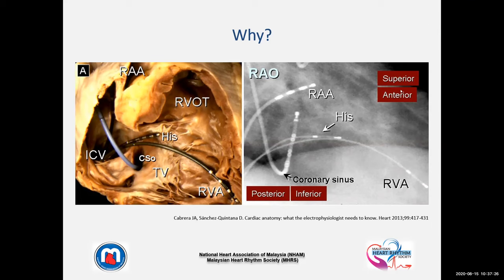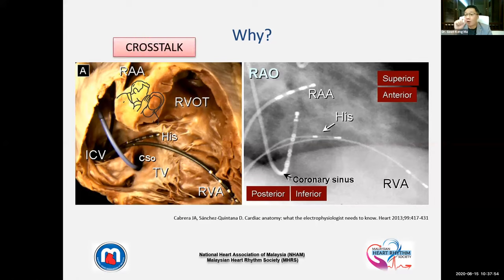Look at this. The right atrial appendage, which is the usual place we put the atrial pacing lead, is right next to the ventricular outflow tract. So if you have a pacing lead there doing its stuff, pacing, causing cardiac electrical activity at that spot, it'll be whispering, talking across the wall towards the ventricle. We call it crosstalk. Crosstalk is the thing we need to avoid in a pacemaker, because you cannot let what happened in the atrium interfere with what's been detected in the ventricle. That's why we have all this refractory and blanking period.